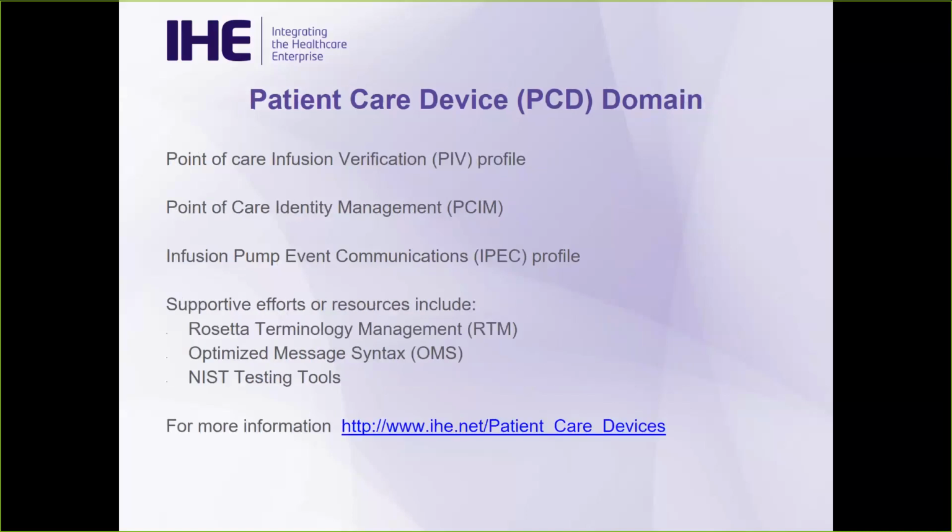We have a few profiles that are involved in infusion management and device identity for all the patient care devices. PCIM represents point of care identity management, and that one focuses on associating automatically collected medical device data reliably with patient information. This promotes the accuracy and completeness of medical device data in electronic medical records.